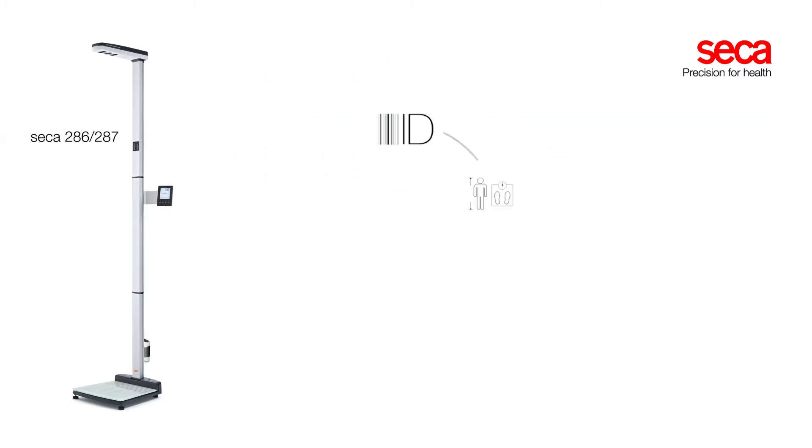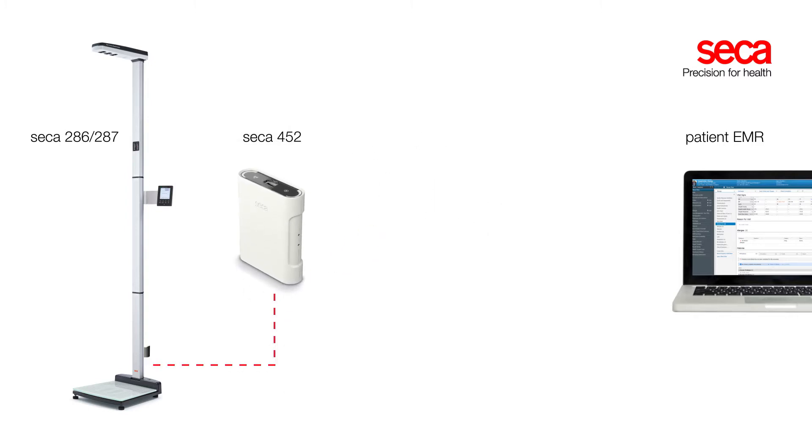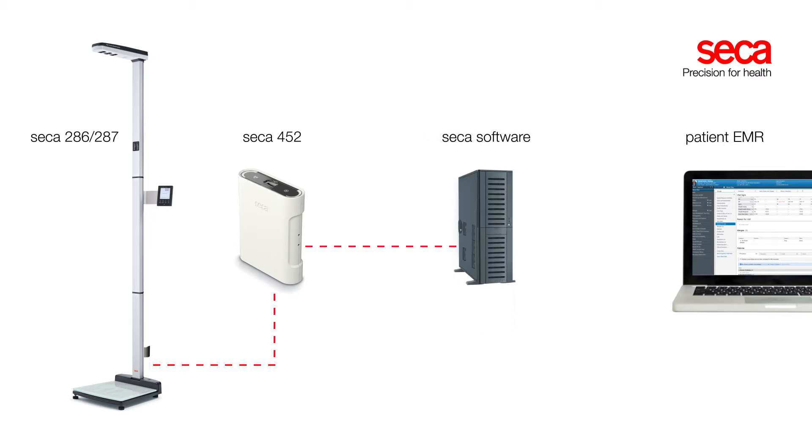When following a defined workflow, the measurements can be integrated into your facility's EMR system immediately with the optional interface module seca 452. The measurements will be transmitted from that module to a central server on the local network, on which the seca software will receive the data and relay it to the proper patient's record in the EMR system.